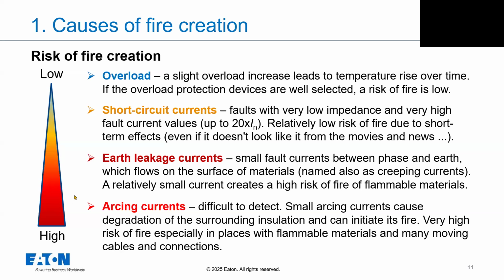Then when we look at the next critical parameter, it's earth leakage current. This is very important during design of installation to take into account, because there is only a very small fault current available between phase and earth, but it affects heating for a longer time. It's also named creeping current, and the problem is it's a relatively small current - for example, 100 milliamps or more looks very low, but it can create fire over a longer time.